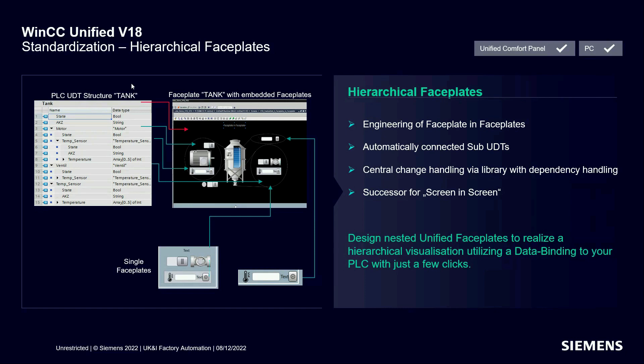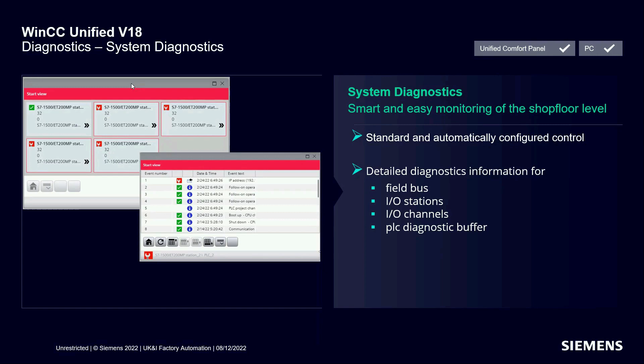Moving over to system diagnostics, you may be familiar with this type of control on the panel side of things - the standard comfort panels. We've now included it on the unified comfort panels, and for the PC-based unified system. One of the really appealing things about the unified environment is a lot of the common functionality our customers want is already done using standard and complex controls. The idea is we can take a standard control out of a library, drag it onto the screen where we want to display it, link it into the PLC, and it automatically makes all the connections, bringing all the diagnostics we need to visualize in runtime. That's exactly the philosophy with the system diagnostic control: it gives detailed diagnostic control down to field bus, I/O, individual I/O channels, and also pulls back the PLC diagnostic buffer - an easy way using low code to get transparency of diagnostics on the visualization system.